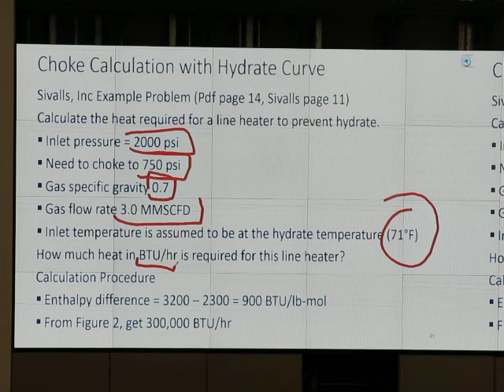Step number 1, we identify the gas gravity. The one in this question is 0.7, so we use the chart that has the right specific gravity of gas. Once we know the specific gravity, we identify the inlet condition. We have inlet at 2000 psi. This is the curve between pressure and enthalpy, H, enthalpy. So we start at 2000. This is the line for 2000.